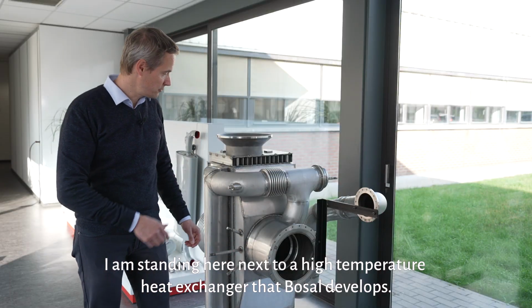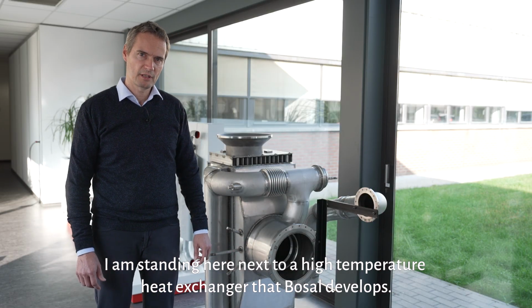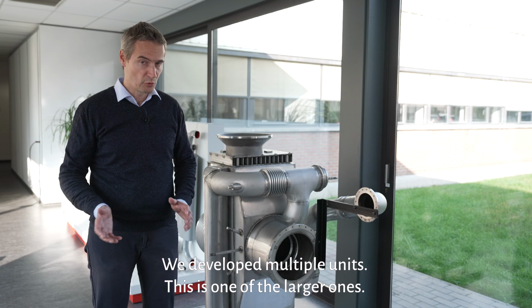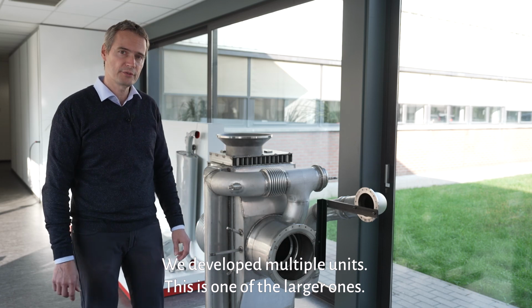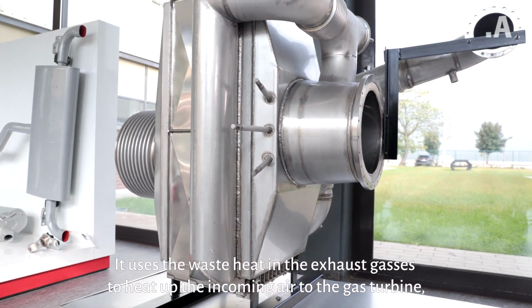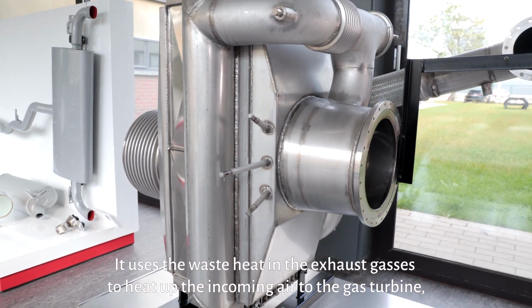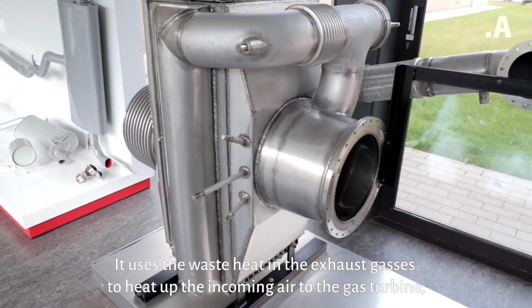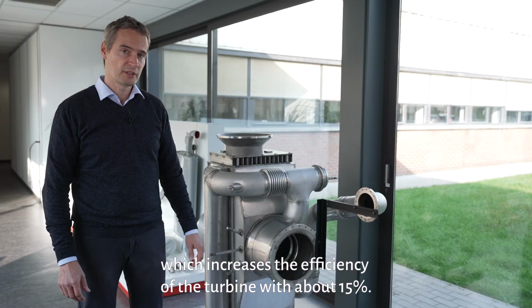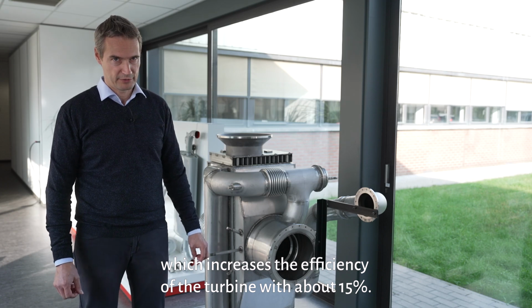I'm standing here next to a high-temperature heat exchanger that Bosal develops. We develop multiple units; this is one of the larger ones. It uses the waste heat in the exhaust gases to heat up the incoming air to the gas turbine, which increases the efficiency of the turbine by about 15%.